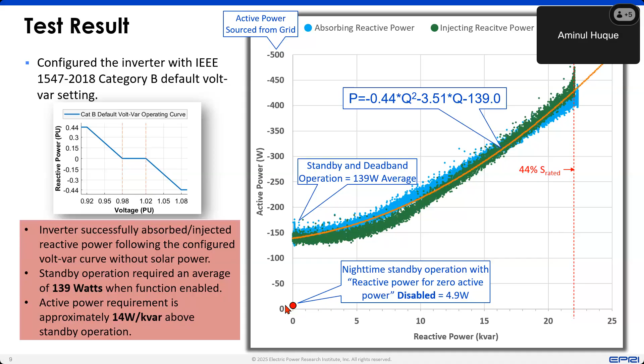I know most of you are on the transmission side of the business, so your interest might be more in transmission-connected, bigger IBR plants. So that's what I'm going to cover next. This is a project that we did with LADWP in California. It's actually a transmission-connected 90 megawatt solar PV project, or plant. It's connected to the 240 kV transmission system. There are some details there, but the main thing is that there are 32 power blocks. Each block is roughly 3 megawatt or 3.3 megawatt.